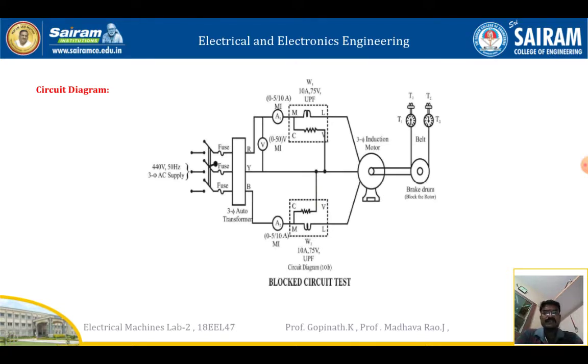In this diagram there is the brake drum, for the blocked rotor test. Before starting the experiment, we should tighten the brake drum with the help of T1 and T2, so that once we switch on, the motor does not rotate and stays blocked. We vary the voltage using the auto transformer up to the rated current, and take the corresponding ammeter 1 and ammeter 2 values, the voltmeter value, and the wattmeter W1 and W2 readings.